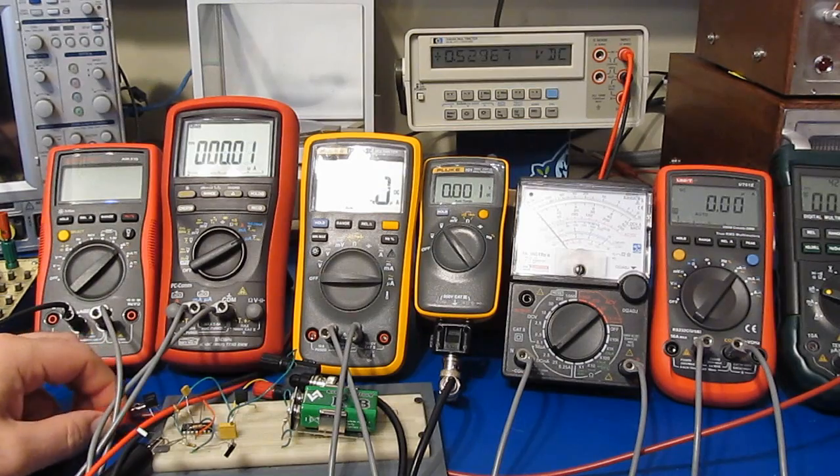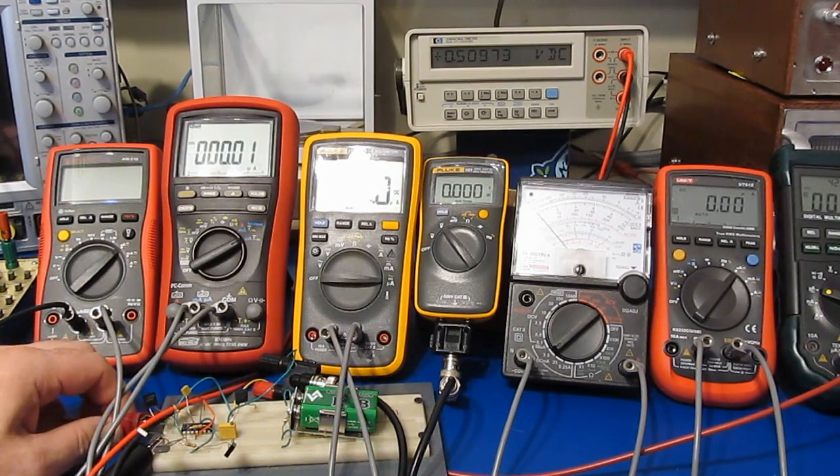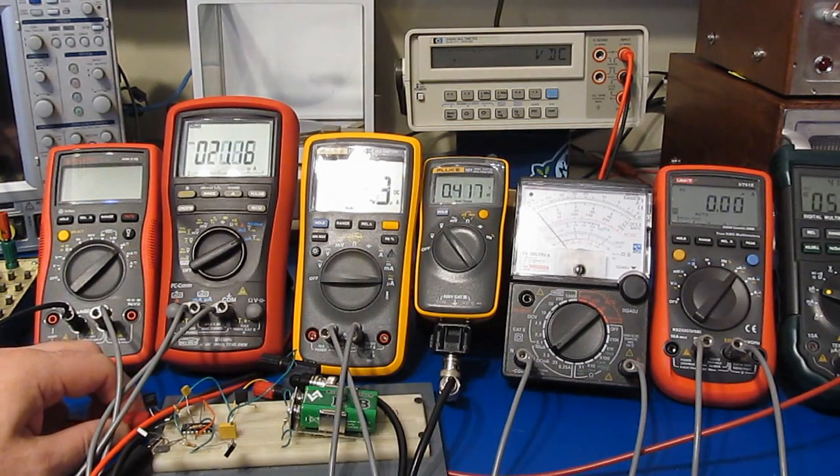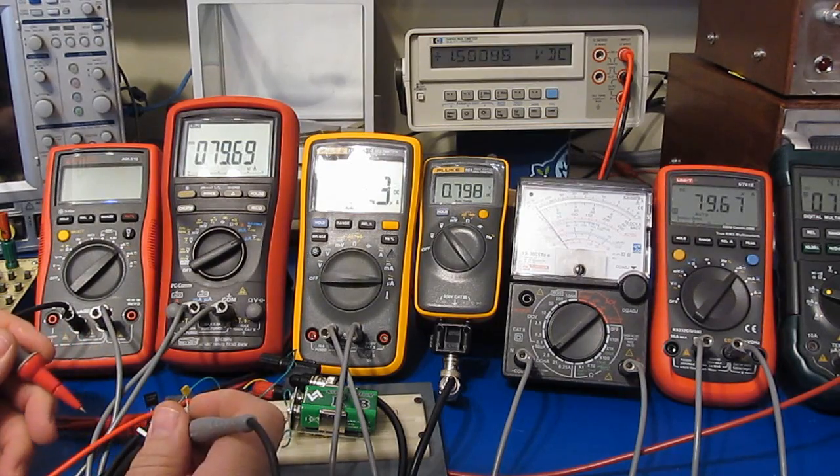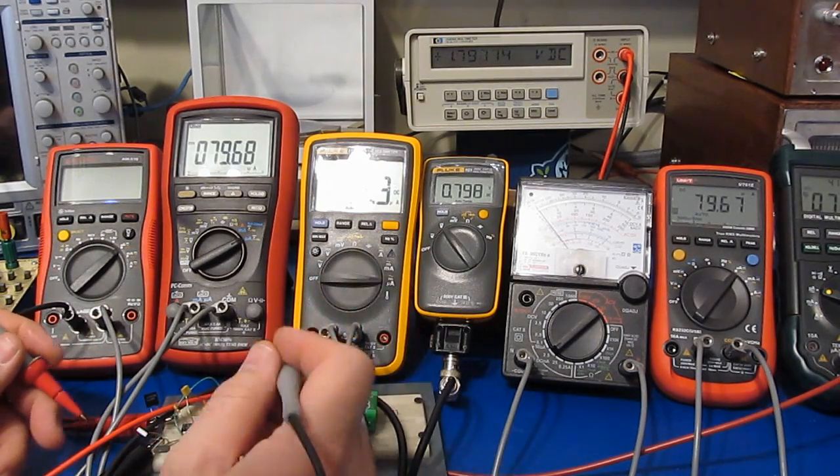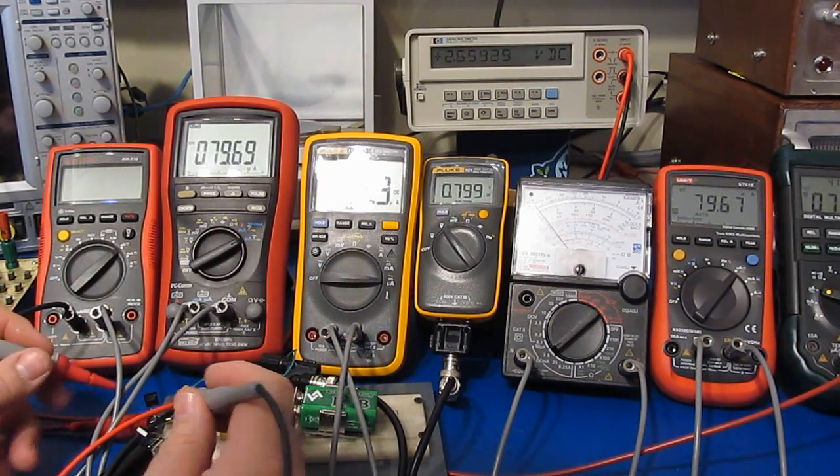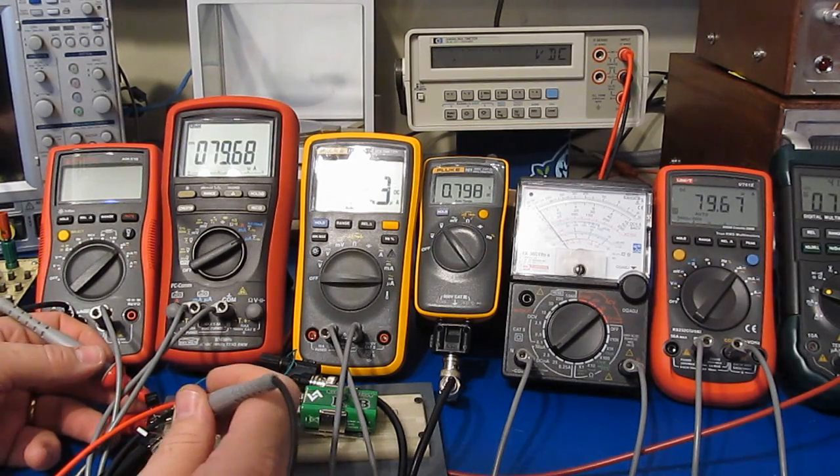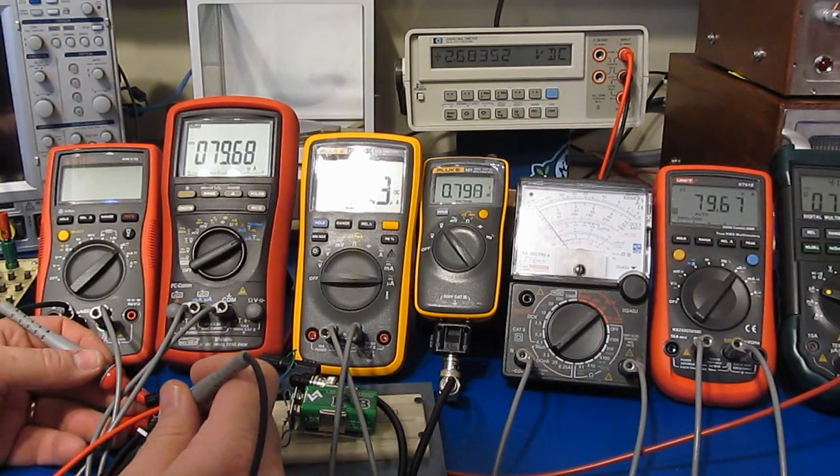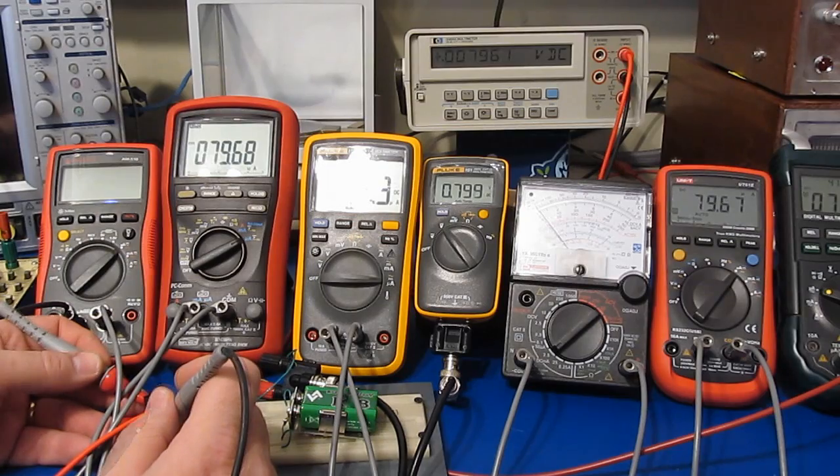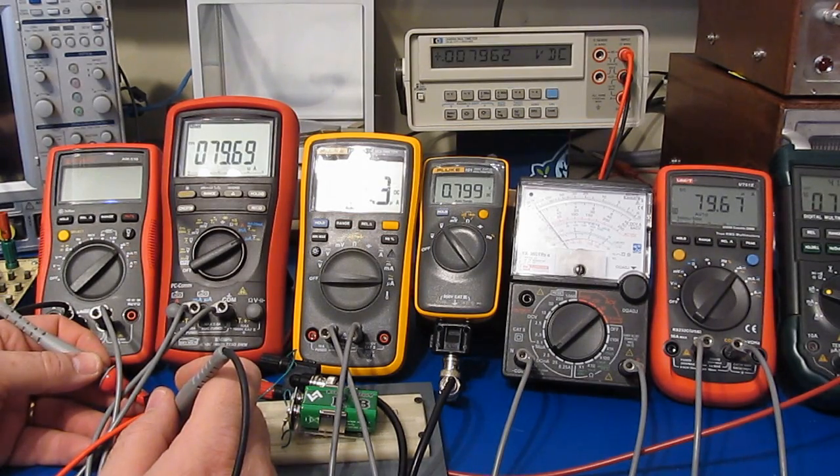You can see I have our little powered shunt attached. And if I disconnect it. See the Fluke 101 now reads zero. If I reattach it. You can see we're getting roughly 798 millivolts. This is a 100 ohm shunt. So if I look across this. You can see it's roughly 79.6 millivolts.